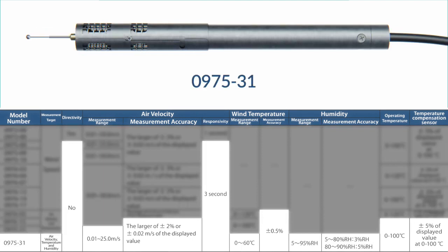And finally, we have the most advanced omnidirectional model, 0975-31. This probe is capable of measuring air velocity, temperature, and humidity. Air velocity can be measured from 0.01 to 25.0 meters per second to the larger of ±2% or ±0.02 meters per second of the displayed value every 3 seconds.